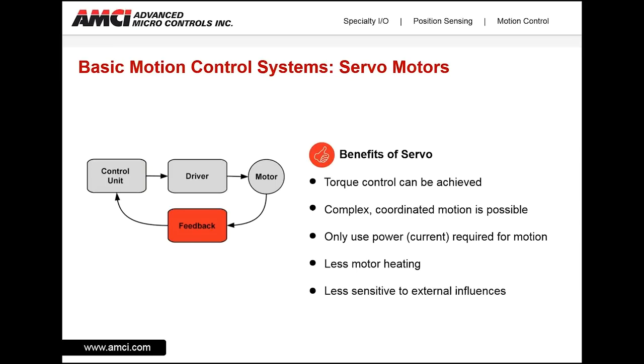Benefits of a servo system are: torque control can be achieved, which in steppers is something that is either very difficult to do or cannot be done at all. They can manage complex coordinated motion because of the feedback. They only use the power or current required for the motion because of the continuous control loop between the feedback and the controller. This reduction of motor current leads to less motor heating. And because of the feedback loop, they are less sensitive to external forces.